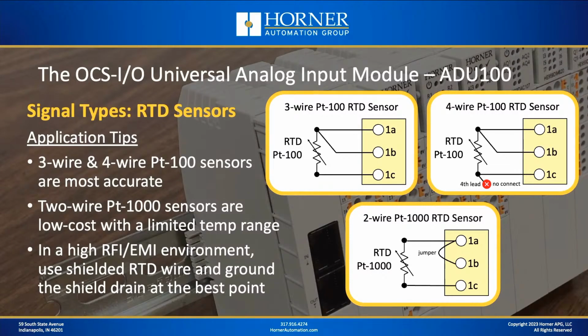Next, let's talk about that diagram at the bottom there, and that is a 2-wire sensor. What's that all about? Well, that's actually a PT1000 sensor that doesn't have 100 ohms at 0 degrees Celsius, but has 1,000 ohms of resistance at 0 degrees, which means that in general, the resistance values are about 10 times what you'll find with a PT100. So because those resistance values are so much higher, the lead wire resistance is really just round-off error that isn't significant, and so a 2-wire sensor is appropriate. Now, one thing to mention about PT1000 sensors, and you'll see that on the next slide, is that they have a much more limited temperature range. In many applications, you'll be tempted just to use standard RTD lead wire, or even just copper wire, between the probe and the measuring instrument, or the ADU100.